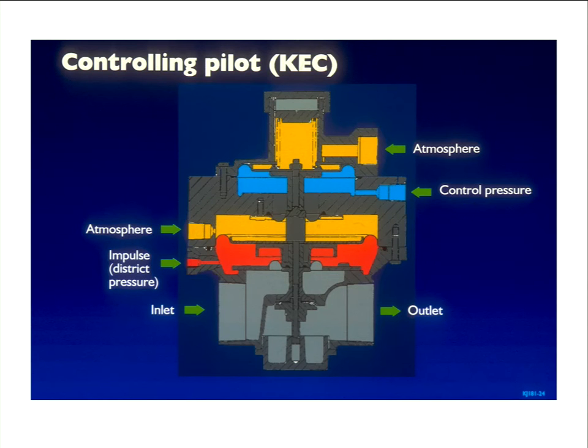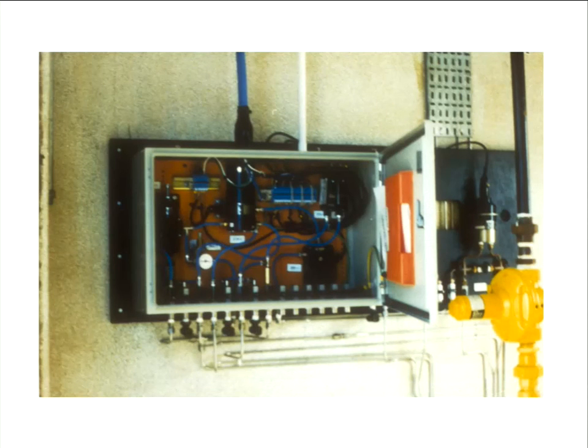And then you get these high integrity pressure protection systems. So typically these are often at boundaries between, say, an importation terminal and the national transmission system, the interconnectors. So things that are operating at quite high pressures, and you can see they're not only making one measurement, they make the same measurement 3 times and then do so-called 2 out of 3 voting, because again, you're starting to look at what might go wrong with that pressure measurement.